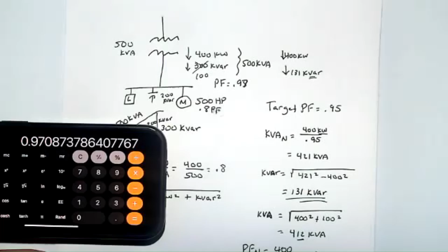Okay, so we went through all these calculations. We showed you some examples of rules of thumb. What are some of the key ones that we pointed out during the actual examples? For 480 volt systems, basically the amps versus kVA is about a 1.2 factor. So if I'm at 75 kVA, I'm about 90 amps. And that's a really important and easy one to remember. So if I'm at 750 kVA, I'm at 900 amps.